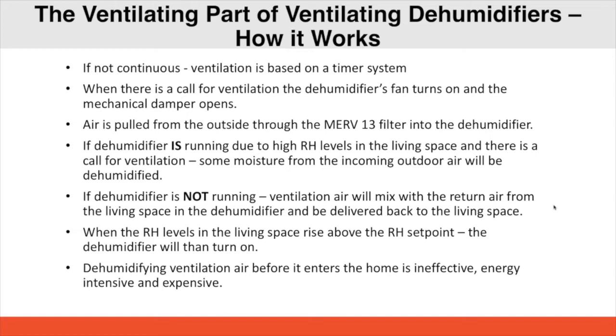Dehumidifying ventilation air before it enters the home is ineffective, uses a lot of energy, and will be expensive. So this is a residential ventilation strategy. I know in commercial there are products that will dehumidify air before it is delivered to the space, but in residential that really is very energy intensive to do. So we really care about what the RH is in the living space, and we're going to bring in that outdoor air, and when the RH in the living space gets above the set point, then we'll dehumidify the entire home. But ventilation through our dehumidifier really is to bring in that dedicated CFM in order to provide effective ventilation to the space.